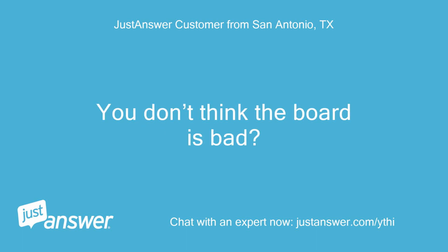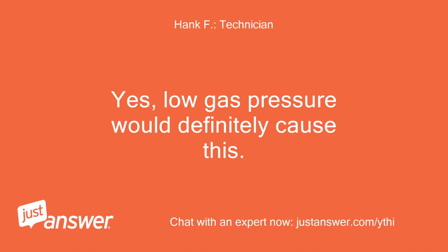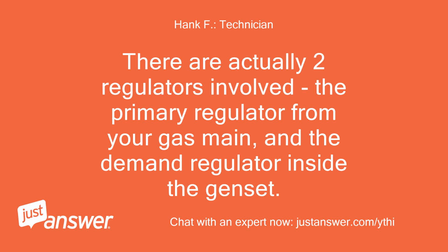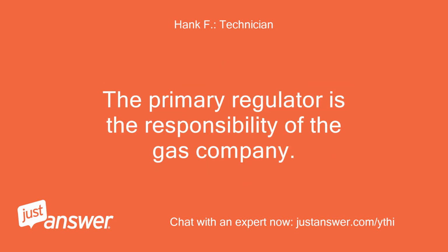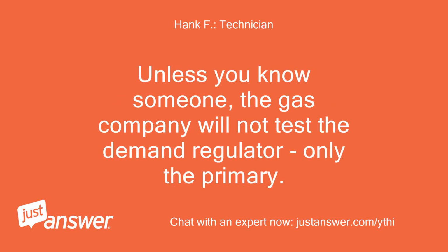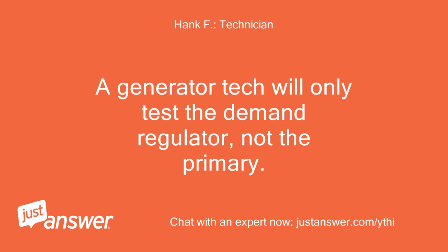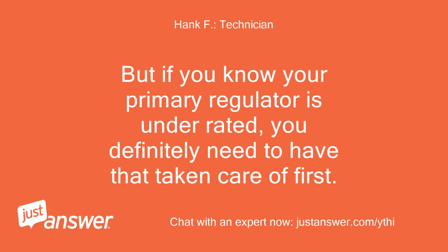You don't think the board is bad? Yes, low gas pressure would definitely cause this. There are actually 2 regulators involved, the primary regulator from your gas main, and the demand regulator inside the genset. The primary regulator is the responsibility of the gas company. Unless you know someone, the gas company will not test the demand regulator, only the primary. A generator tech will only test the demand regulator, not the primary. But if you know your primary regulator is underrated, you definitely need to have that taken care of first.